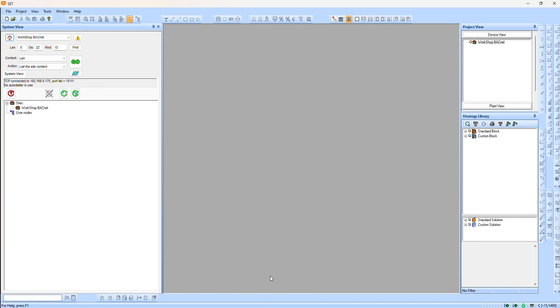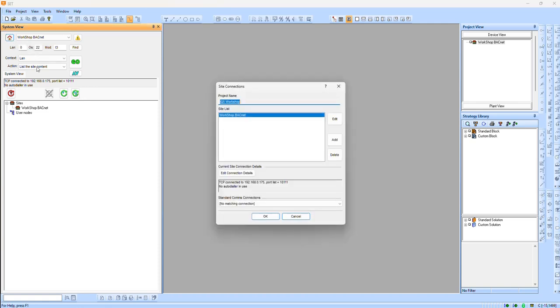That is in the SET installation directory. You'll find there's one under there called BACnet.msi if you look for it. If you install that, it installs a BACnet comms agent, which you can then use as a BACnet Explorer within SET. First and foremost, though, I'm going to connect to my IQ5s and bring those in, and then we'll connect to the BACnet site and see what that shows us.